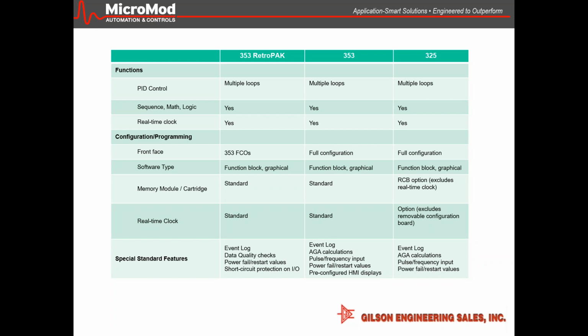In your power failure and restart, you can set predetermined values. You have the ability to do cold start, warm starts, hot starts. And probably one of the more interesting things is that it actually has short circuit protection on the I/O. So in the event that a wire were to become compromised, you would get an error, and it would tell you what that error is. It's a very elaborate messaging system, and that can be sent to a SCADA. It can also be displayed on an HMI.